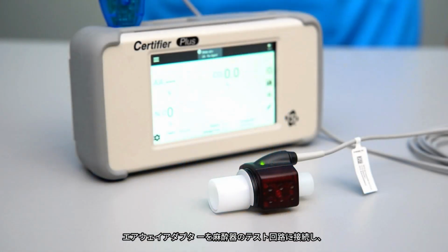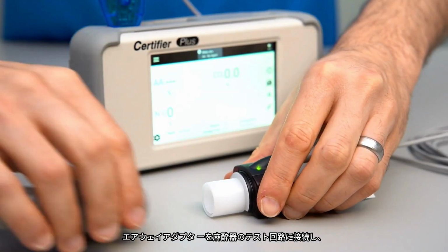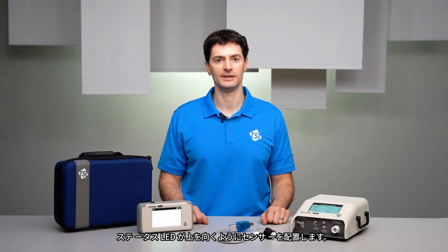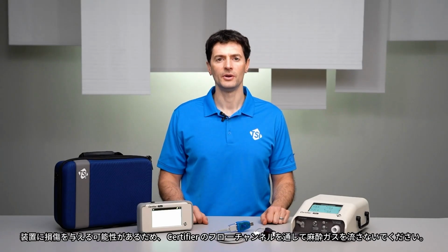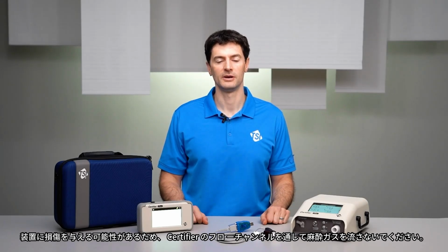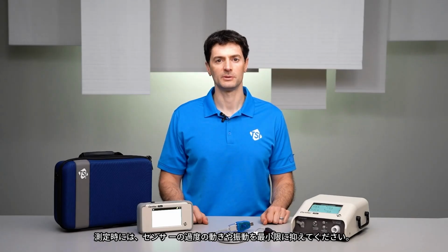Connect the airway adapter to the anesthesia machine test circuit and position the sensor with the status LED facing up. Note that you should never run anesthetic gases through the Certifier flow channels, as this may damage the instrument. While making measurements, minimize any excessive movement or vibration of the sensor.